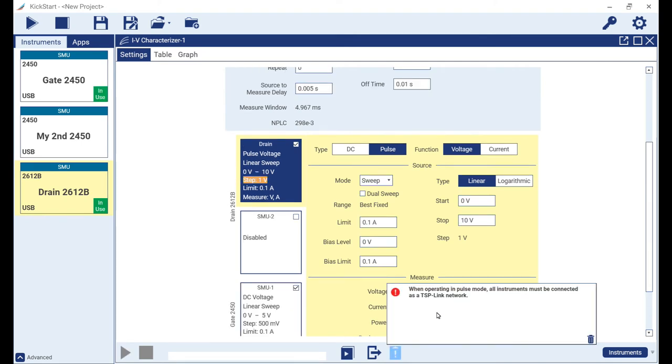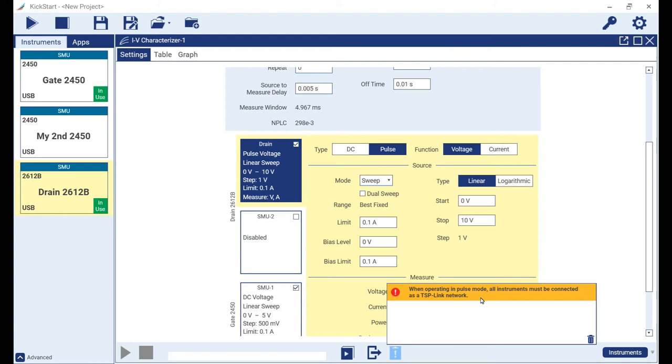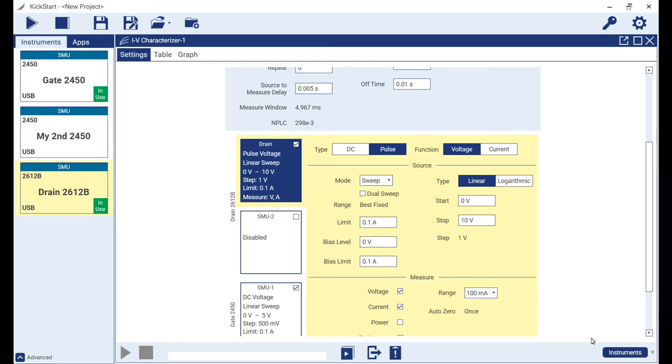Note the error message that is being presented. To allow the 2600 series SMUs to work in concert with the 2400 series graphical SMUs when pulse mode is involved, the TSP link connection must be made using the TSP link cable to connect the two instruments. For DC mode operation, the TSP link cable is optional.